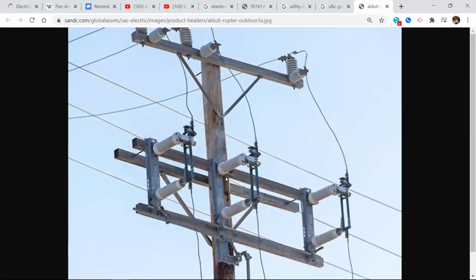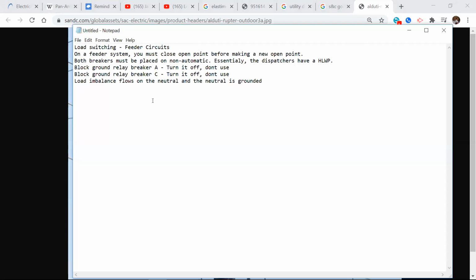I know it's kind of long in the explanation right here. While you're operating switches, opening and closing any kind of switch, either a gang-op switch that you're looking at right here, or regular static disconnects that you have to open up one at a time, of course, that's going to take more time. Every time I go to the open procedure, there's going to be load imbalance. Load imbalance is going to flow on the neutral, and the neutral is grounded on these systems that we're talking about. The ground relay is going to detect it. It's going to open the breaker. Do we want that to happen? No, because then you've lost all the customers anyway. Yeah, then you've lost the customers on both circuits. Remember, you were trying to tie two circuits together. So you've lost the customers on both circuits.